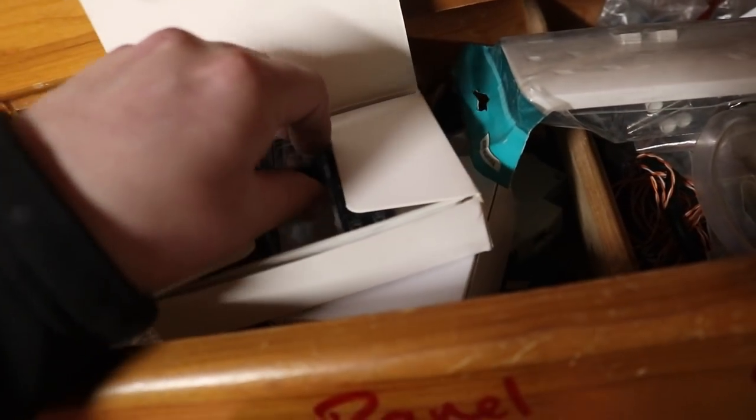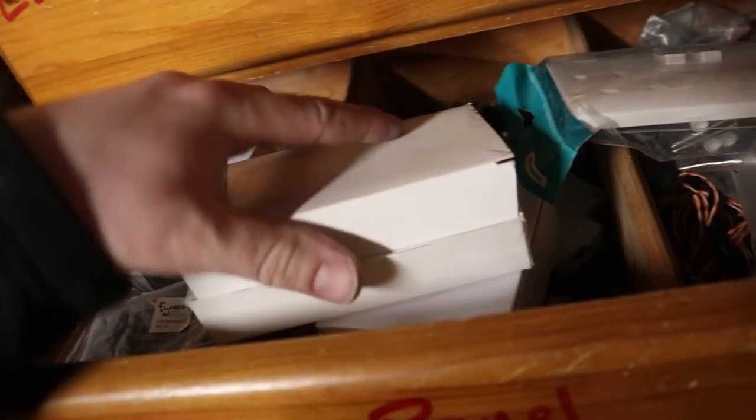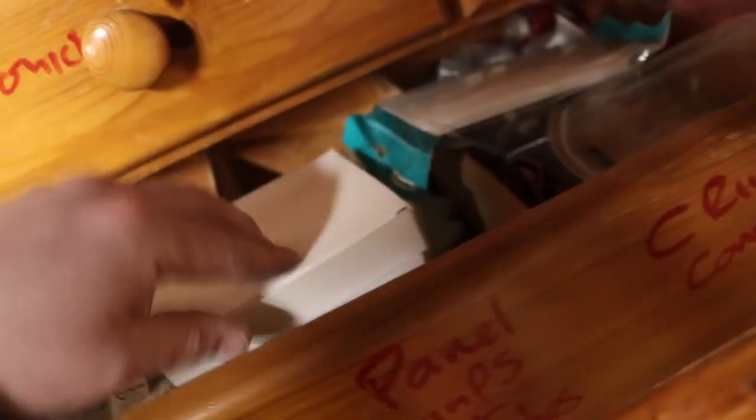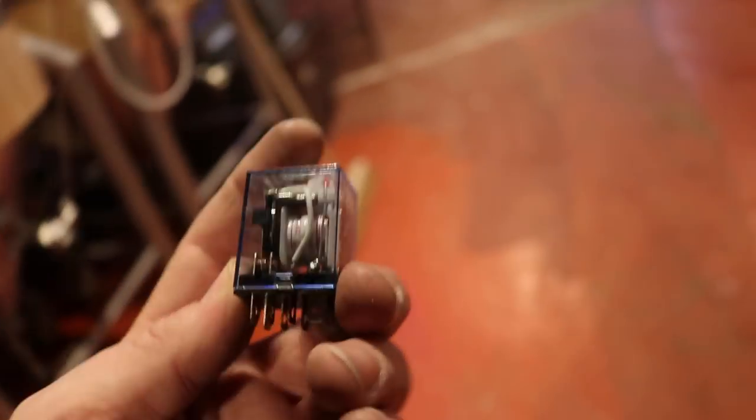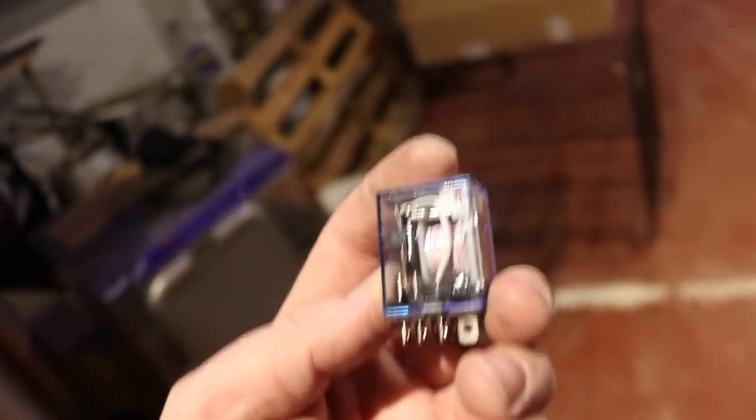So I was at the other end of the unit, just doing a little bit of tidying up after cutting that wood, and I noticed that the cooler for the tanks had chilled the glycol to minus 20 degrees centigrade, which, well, considering it's set for -7, is a considerable amount colder. And of course it was a failed relay. I've just thrown it in the bin. Let's see if I can fish it out.